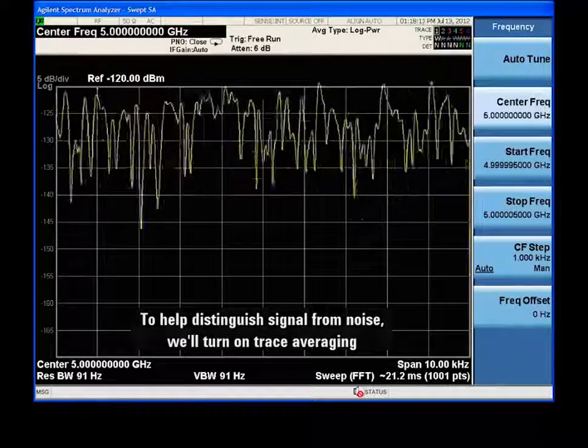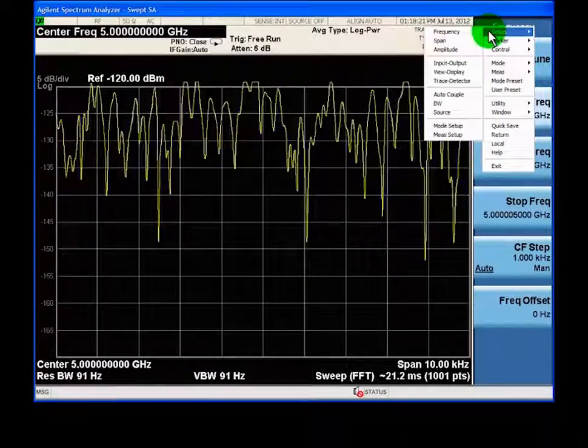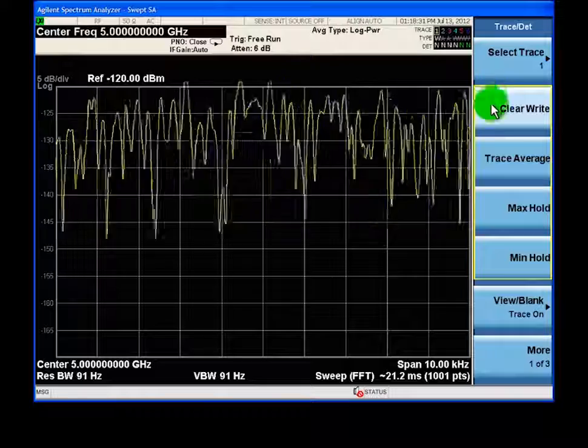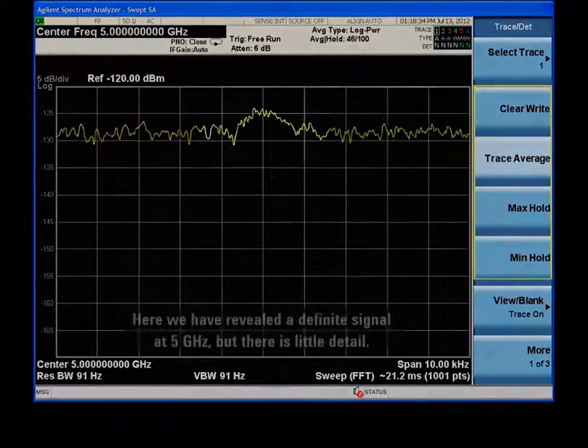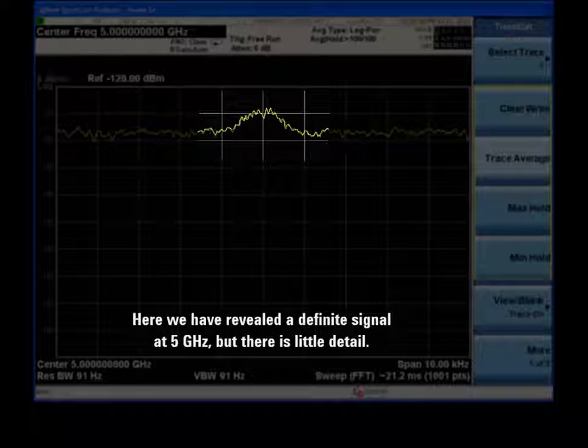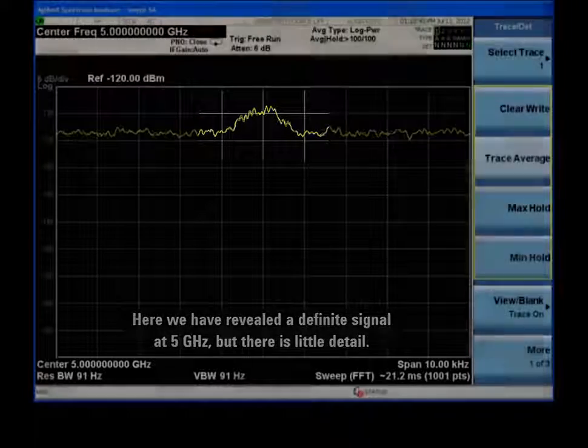We'll turn on trace averaging, which can help identify steady signals in the presence of random noise. With trace averaging turned on, we can confirm the presence of a signal at 5 GHz, but we don't see much detail.